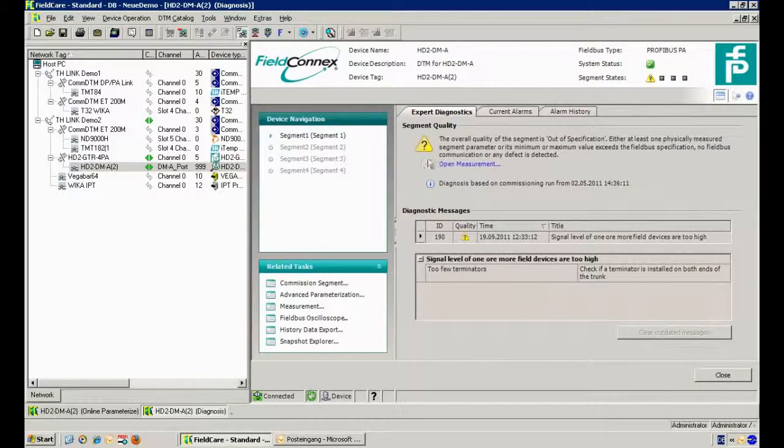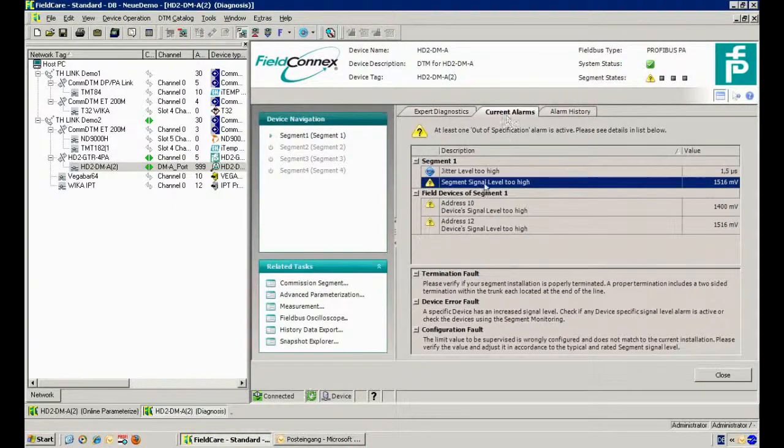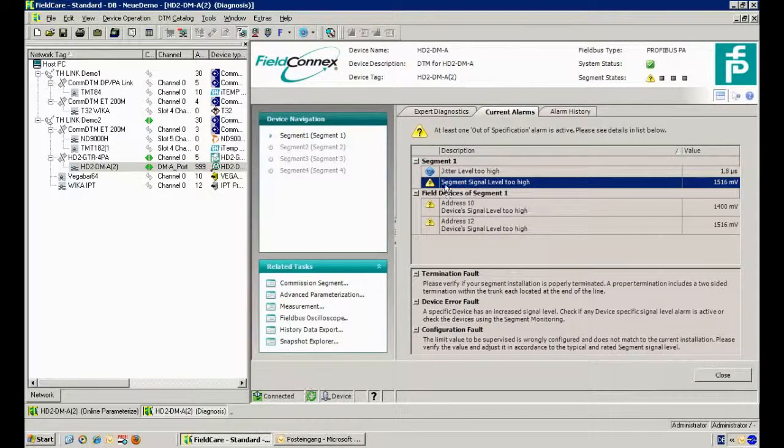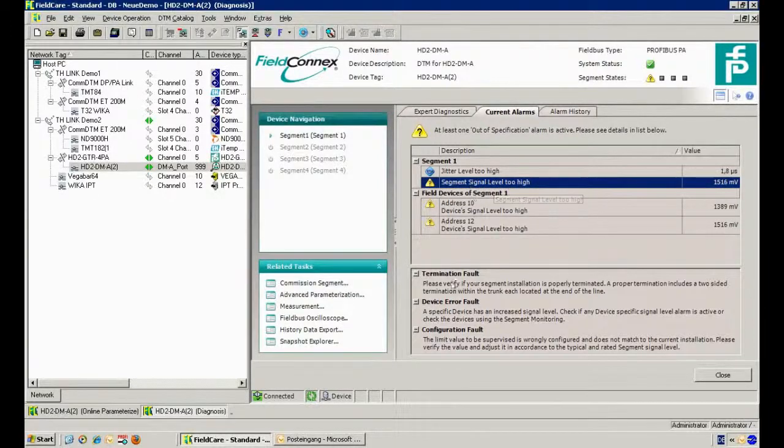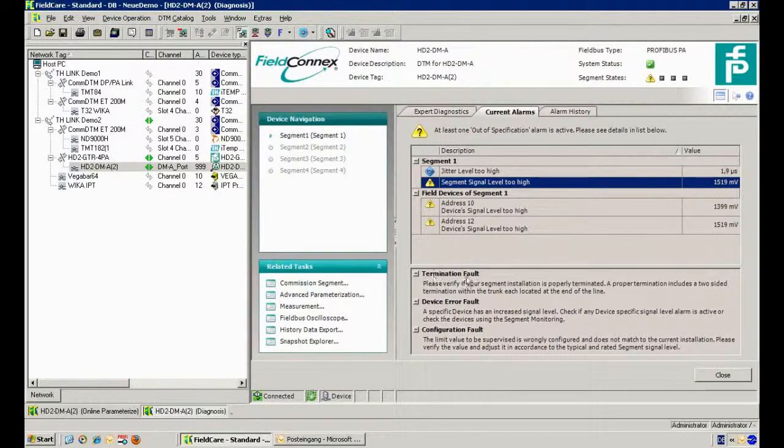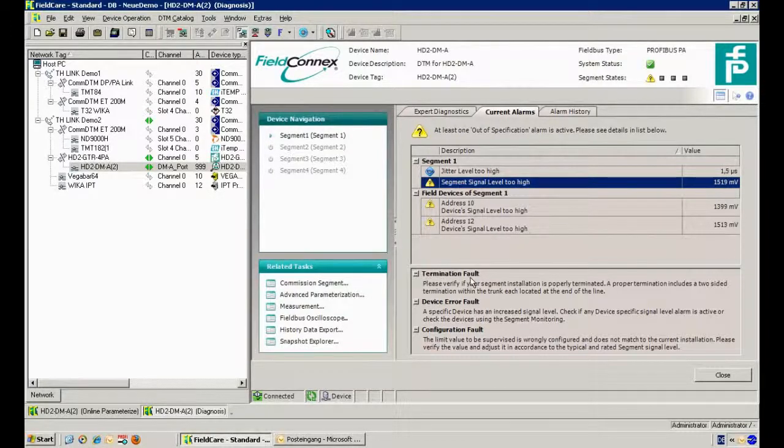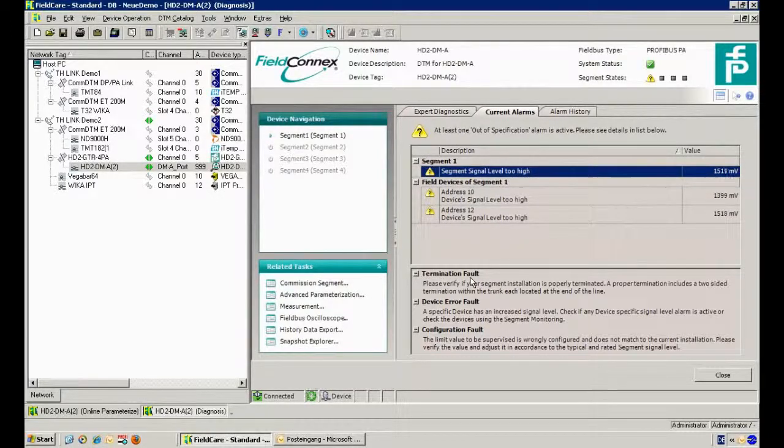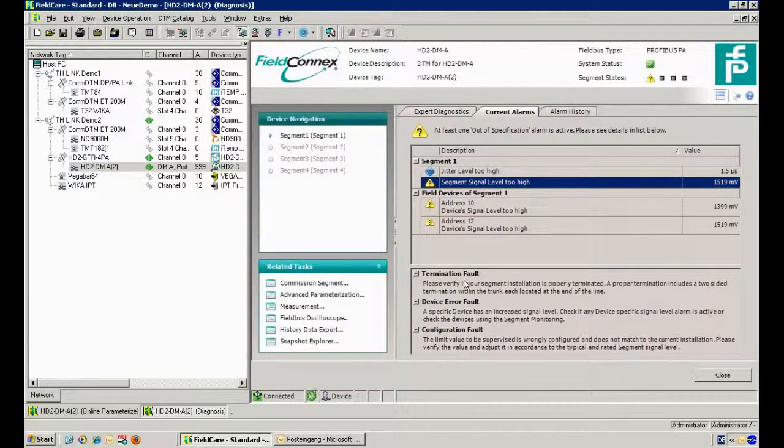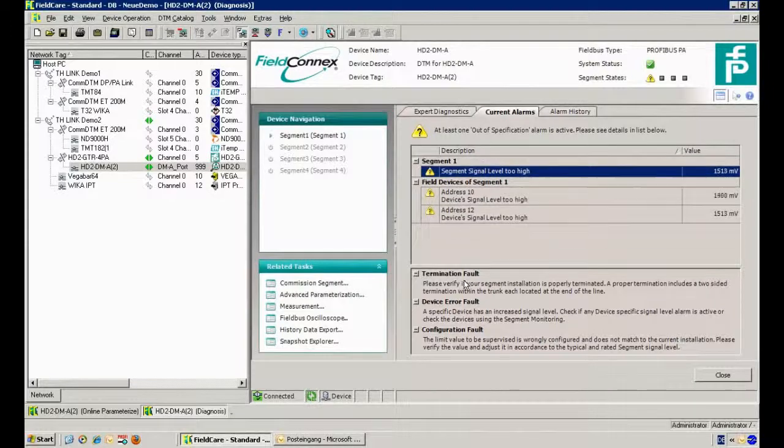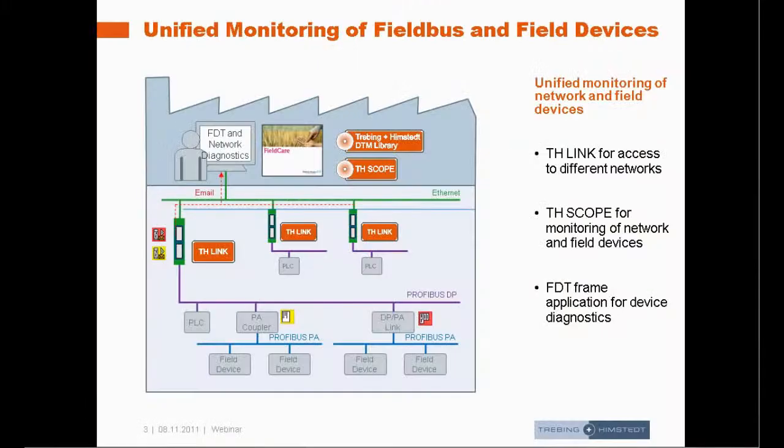What we see here is segment signal level too high. One of the possible root causes could be a termination fault, so we get a list of possible root causes for this problem. This termination fault is the right message in this case, as we switched off the termination to simulate this error.